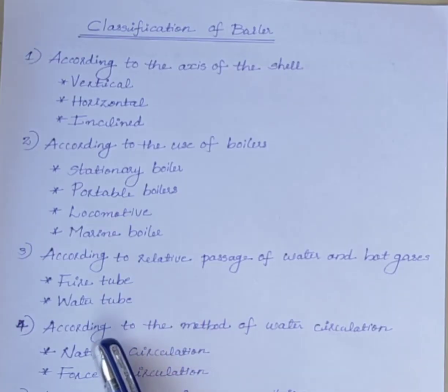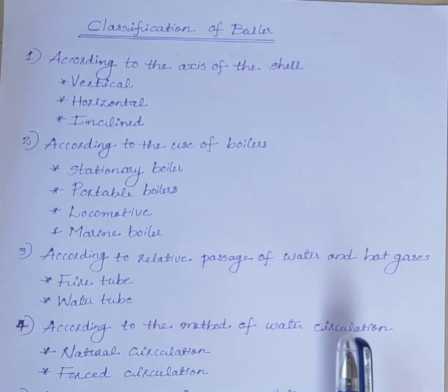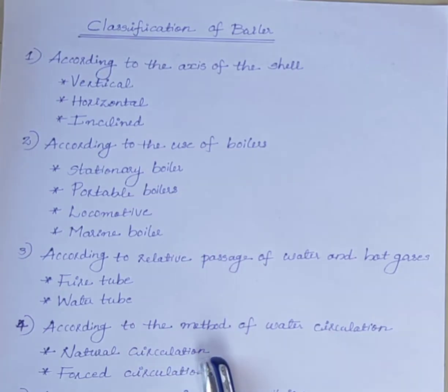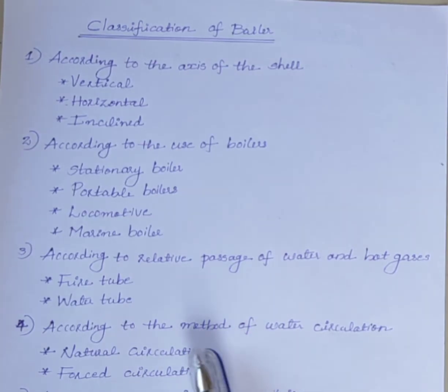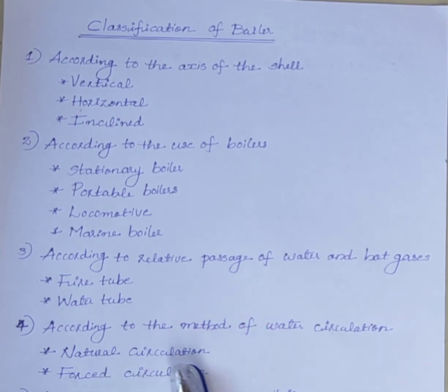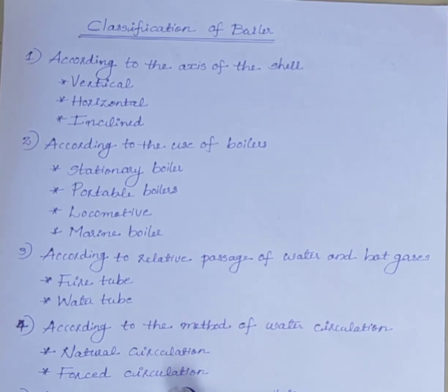The next classification is according to the method of water circulation: natural circulation boiler and forced circulation boiler. If the circulation of water or steam is caused by a density difference — due to temperature variation — it is called natural circulation. In forced circulation, a water pump forces the water along its path.